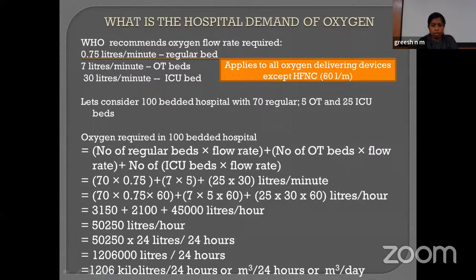If you multiply by 24, you get the oxygen requirement in a day. For this hospital, it is around 12,06,000 liters per 24 hours. Or you can say 1,206 kiloliters per 24 hours, or 1,206 cubic meters per day. So we now know the hospital requirement.